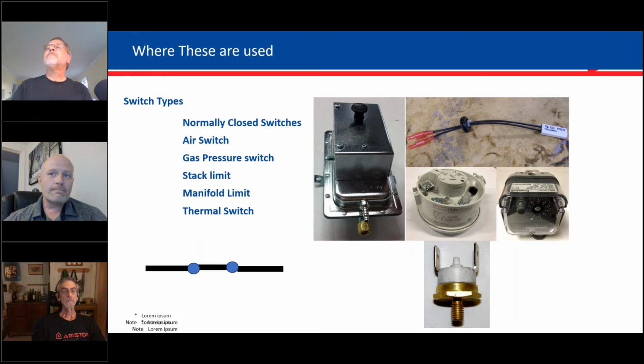And that was there for safety, right, Dave? Well, yeah, the reason it's there is in some cases, if the boiler is reassembled incorrectly, if a gasket fails or the burner door refractory fails, the burner door can become effectively red hot. And this switch is designed to prevent any serious damage if that does occur. So one thing I will say, guys, is if you do see these thermal limits tripping, although they are resettable, they're a bit like the airbags in your car. It's probably more than just a minor fender bender that caused it to trip. It is a pretty serious indication if you see a thermal limit trip. So watch out for that. It's not just, oh, I'll reset it and get back to it next week. It probably should be addressed right away.